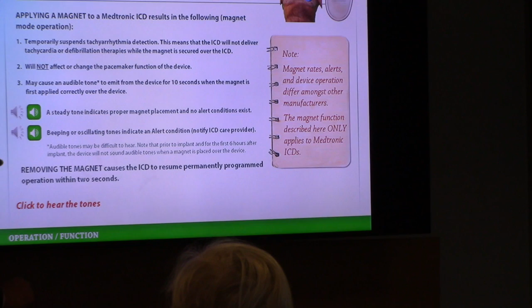So in the same situation, patient having surgery with an ICD, you would put a magnet on because the cautery will cause noise on the lead that might be construed as a ventricular arrhythmia, and therefore the patient might get an inappropriate shock. So whenever an ICD is involved, the magnet only suppresses or suspends the therapy. It doesn't do anything to the pacing function. It's very critical that you understand this. Okay?